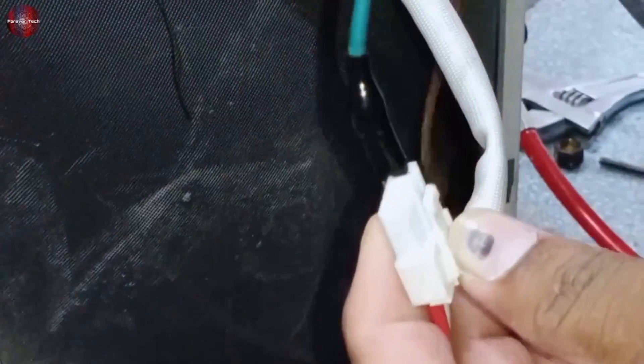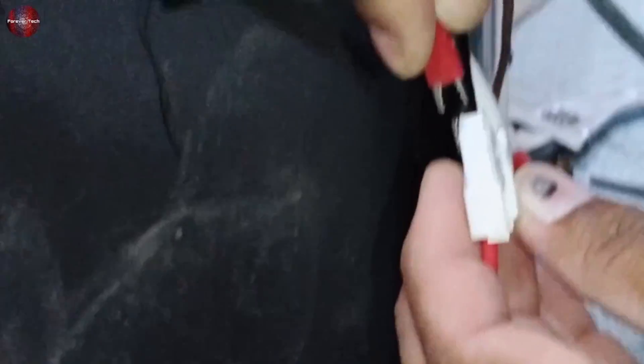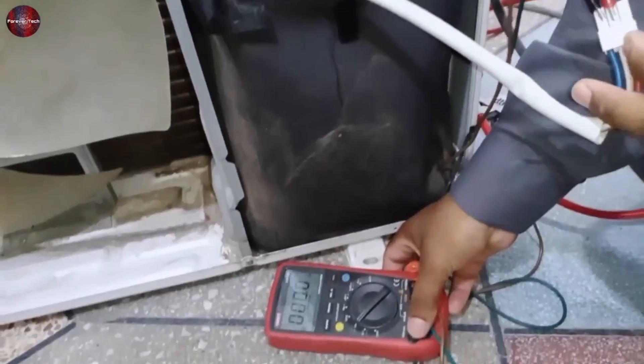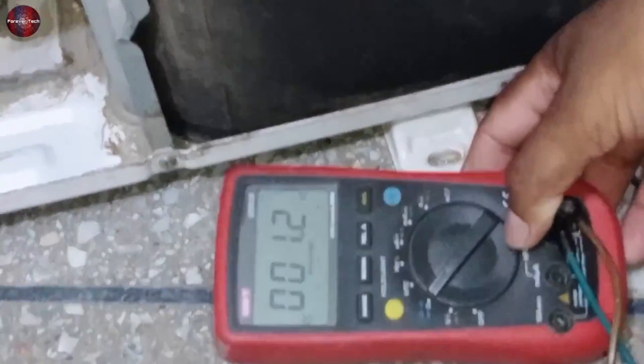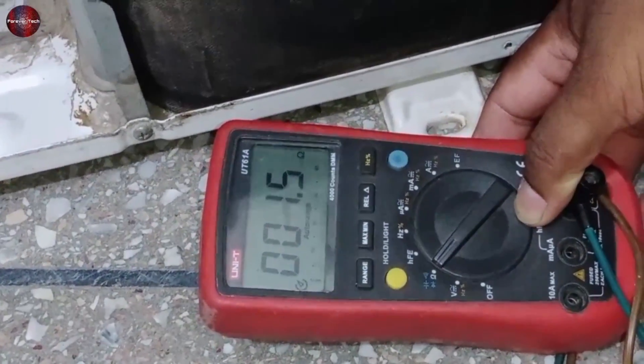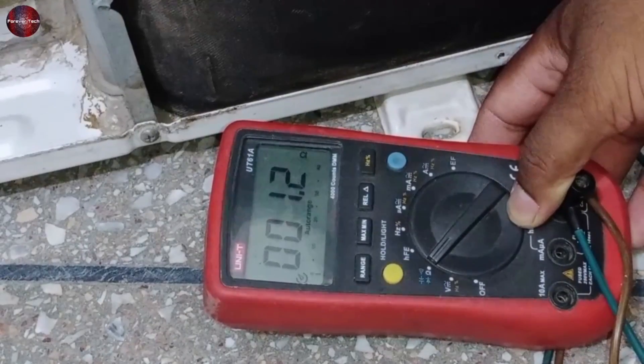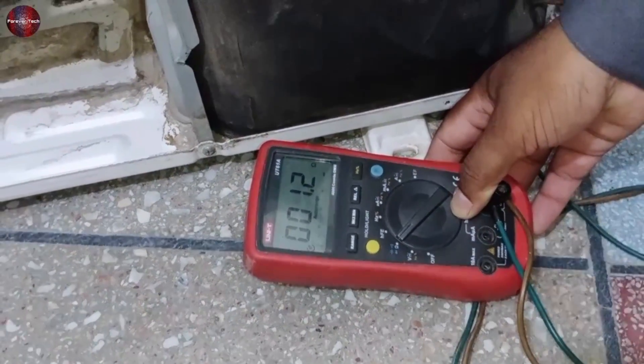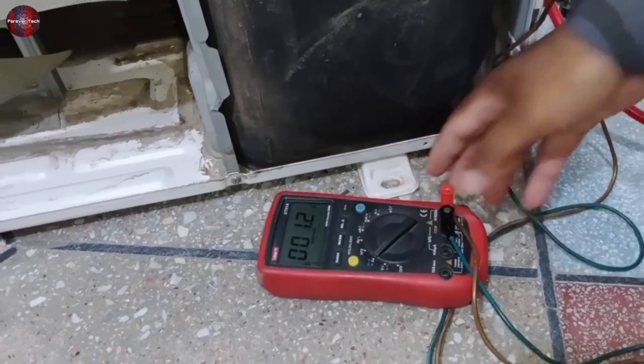Attach the first probe to any terminal of the compressor and the second probe to the next terminal. And see, the multimeter has started showing us the compressor's reading. We are getting the value of 1.2 ohms on the multimeter with these two terminals. Note down this value.